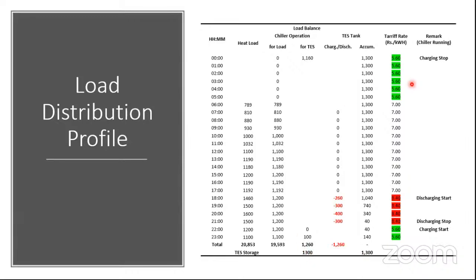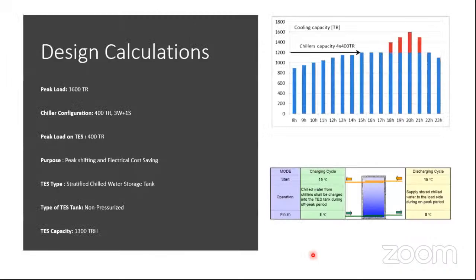I would also like to draw your attention towards this column, which is the tariff rate. It is also a key factor in how we should plan our discharge pattern, and in what hours we should try to avoid running chillers as far as possible. What is the most optimum operating strategy to be applied? That's how we arrive at the thermal storage capacity. You see, it's 1300 ton hours in this case, so our design calculations will be based on this.